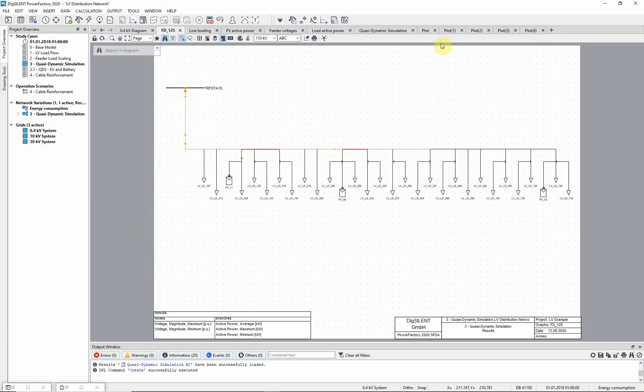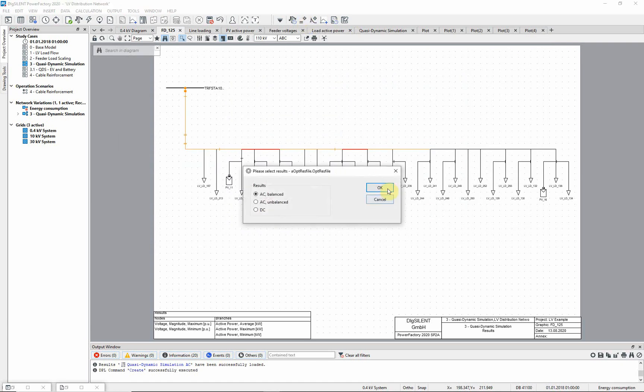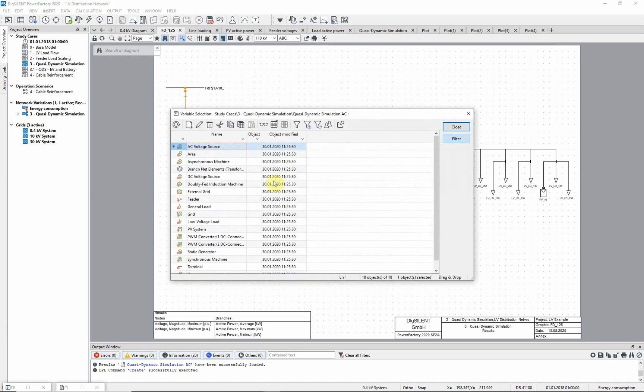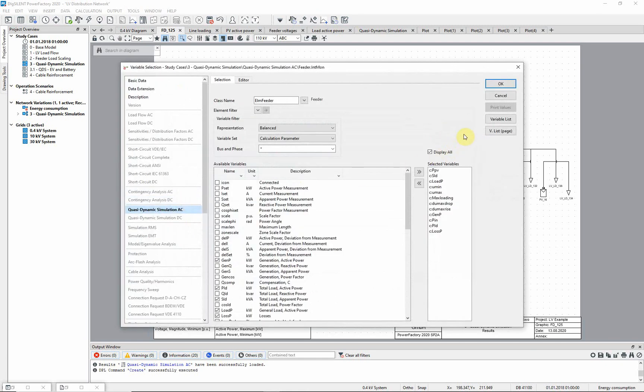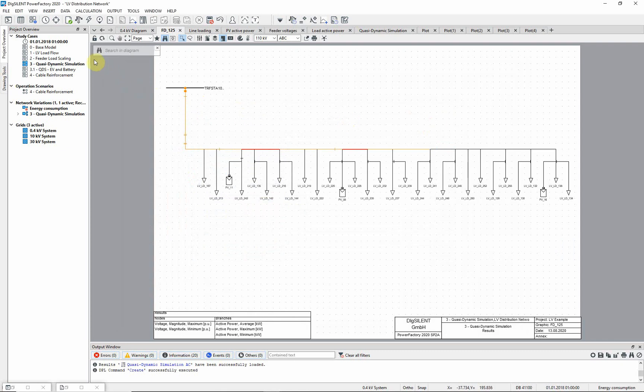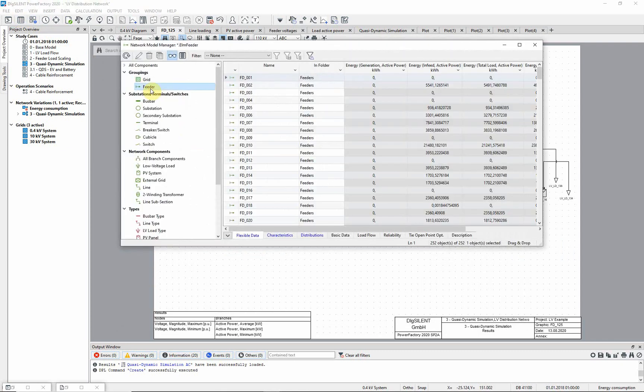Click on the edit result variables icon in the quasi-dynamic simulation toolbox. Choose the AC balanced option and double-click on feeders in order to open the variable selection. Notice that some calculation parameters are already defined: GenP is the power of all generation units, PIN is the in-feed from an external grid, PLD is the power of all loads within the feeder, and LOSP is the overall losses within the feeder. Open the Network Model Manager and select the feeder class. Go to the flexible data page — here it is now possible to select the calculated energy values, which correspond with the previously selected power values.